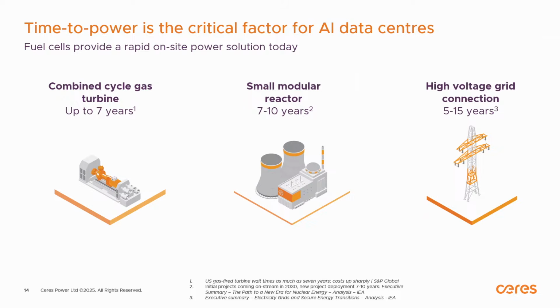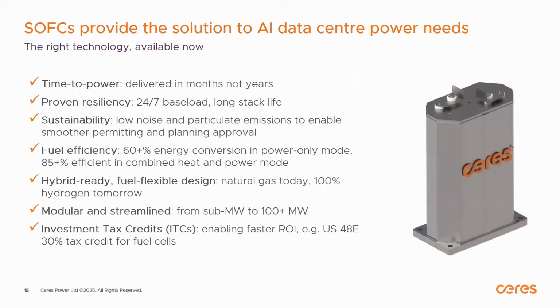And why is SOFC good at this? The efficiency is really good. A gas turbine is 35 to maybe 45%, maybe a little higher. SOFC will go up to 60%. And if you're using it in industrial power and can use the heat for combined heat and power, that efficiency goes up too. So it is quite compelling, and that's why our partners really like this kind of technology and have taken licenses.